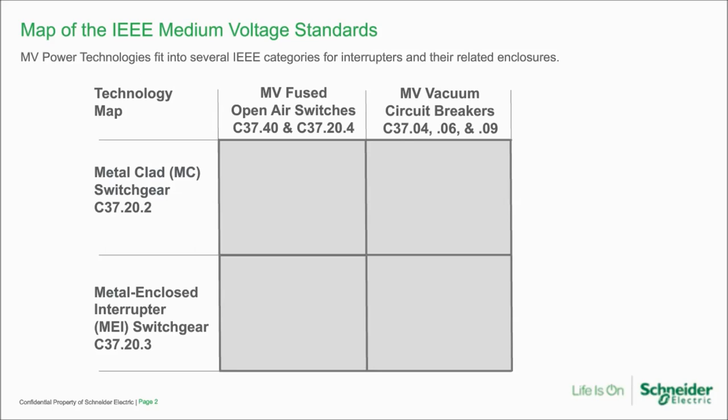The column on the left is for fuses and related upstream maintenance switches; the column on the right is for circuit breakers. According to IEEE, users have to reference all three of the following standards to properly select their breakers: C37.04 for ratings, C37.06 for preferred ratings, and C37.09 for the qualification test procedure. These are IEEE standards adopted by ANSI, and they are primarily where we look in terms of technologies to fit against applications for NEC.